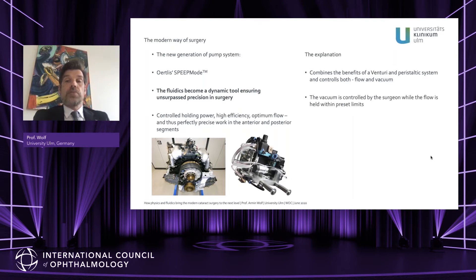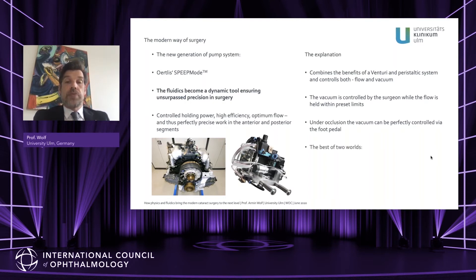While the vacuum is controlled by the surgeon with the foot pedal, the flow is set to its preset limits. So under occlusion conditions, the vacuum can additionally be perfectly controlled via the foot pedal, which is not possible in other pump systems. Thus, the SPEEPMode combines the best of two worlds and gives you very high speed and efficacy at the same time.